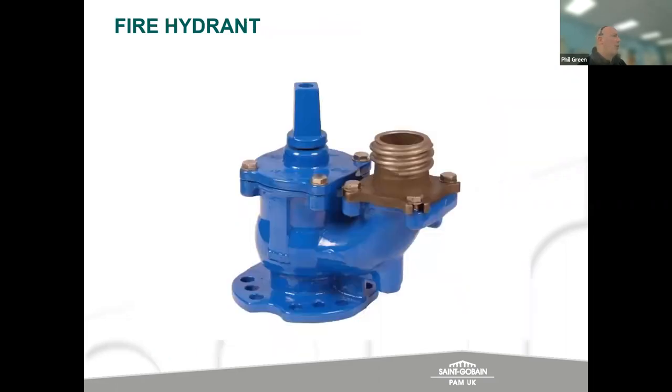So again, looking at a hydrant, that's what it looks like. This particular example is what we call our squat version. And if you see there on the outlet, that sort of gunmetal piece is the outlet type, and that's the London round thread type of outlet. So again, from a UK perspective, that's been standardised as part of the UK fire services standard outlet. So every fire brigade in the UK has a connection that will fit to these to enable these to be used without any sort of interface or check. Or challenge, let's say, because if there's a fire, you want to be able to connect to it quickly, which is why it's been standardized to that particular shape and thread type.